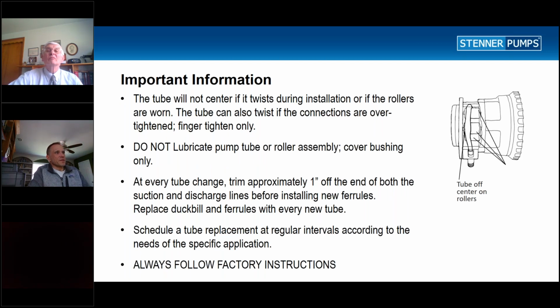So a few things you don't want to do, just to remind people: don't lubricate the tubes. Make sure the tube's centered. If you need to center the tube, we recommend turning it a little bit on one end, just to try to walk it through on the rollers. When you're changing the ferrules, we recommend just cutting off the end of the tube to get a nice, clean, straight seal. And then also change the duckbill when you're changing the tube.